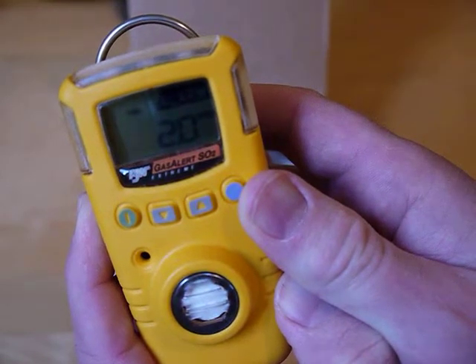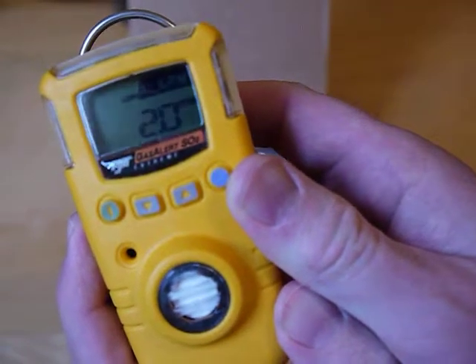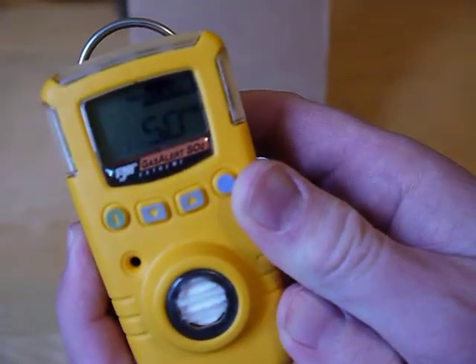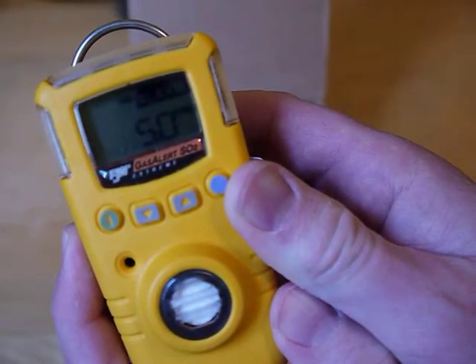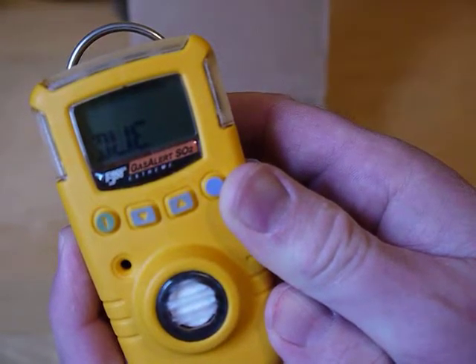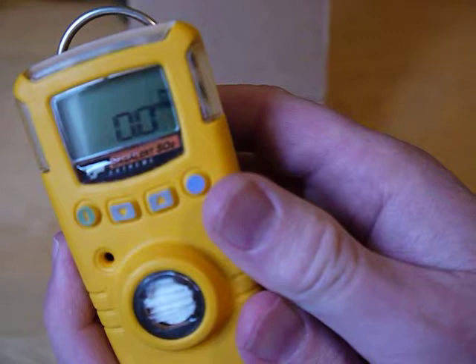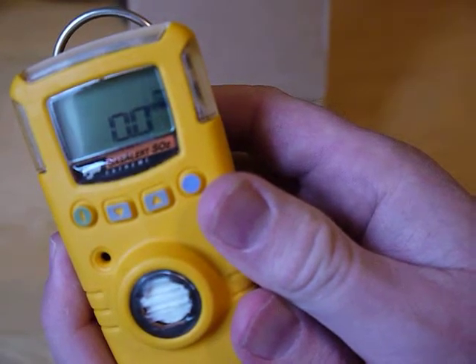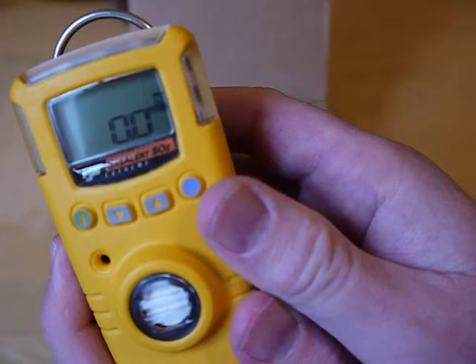It's showing the TWA alarm, the STEL alarm, the low alarm, the high alarm, and calibration due in 155 days. Some customers calibrate every month; Honeywell states it can go up to 180 days. Either way, you would bump test every day before use.